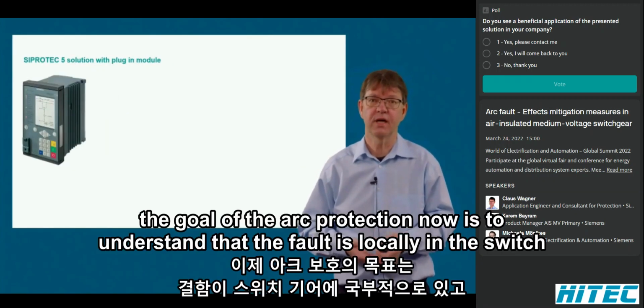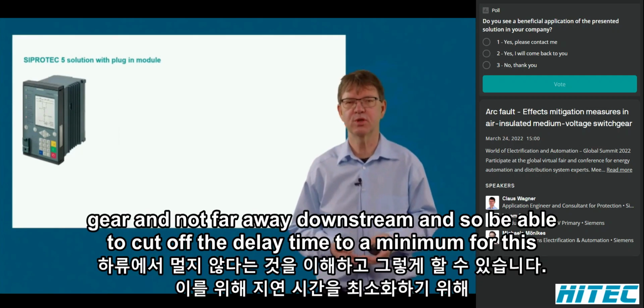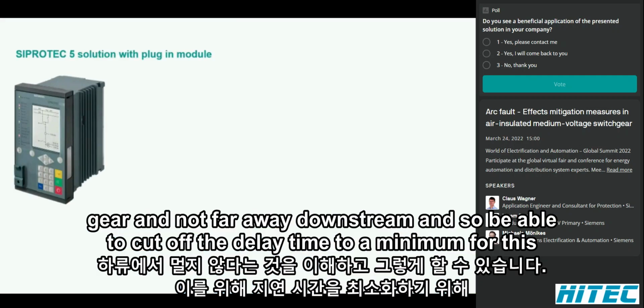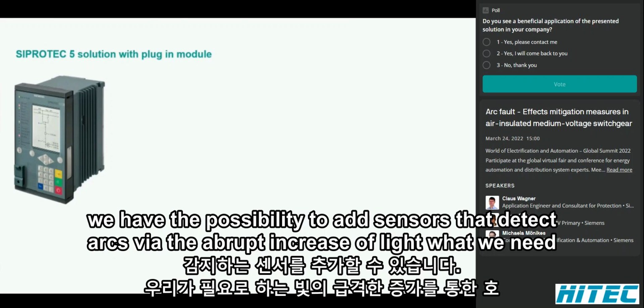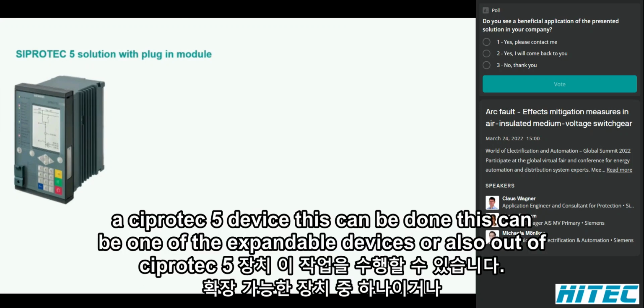The goal of the arc protection now is to understand that the fault is locally in the switchgear and not far away downstream, and so be able to cut off the delay time to a minimum. For this, we have the possibility to add sensors that detect arcs via the abrupt increase of light. What we need? A SIPROTEC5 device. This can be one of the expandable devices, or also out of the 82 family, our non-expandable SIPROTEC5 branch.